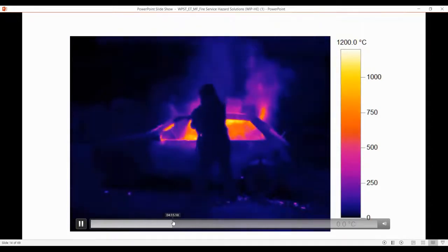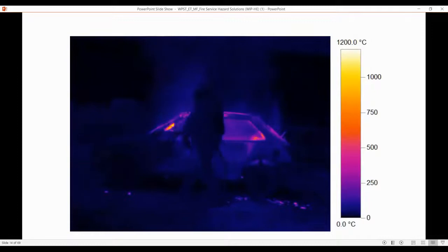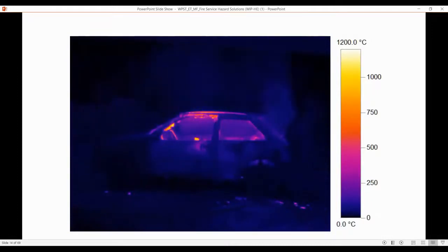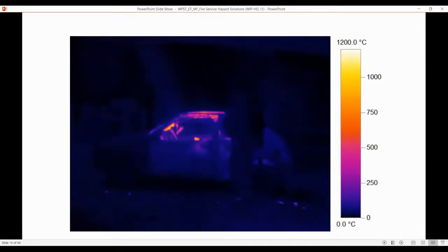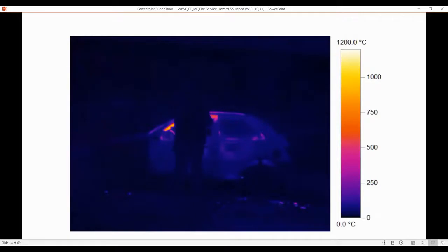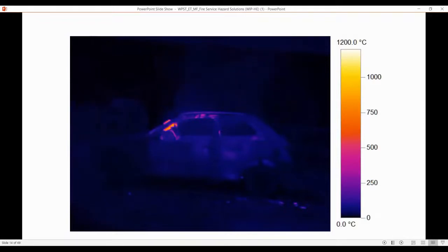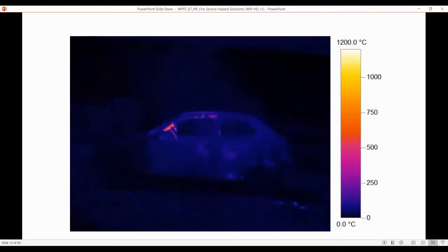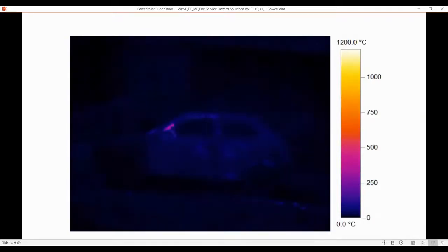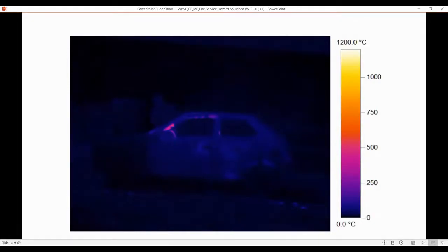Now the firefighter in this video is going to be using a 20-gallon per minute self-educting nozzle. As you see here, as soon as he starts attacking the fire, you have rapid knockdown and rapid cooling. You can see the heat being dissipated out of that metal, how rapidly it's doing it with very little water, very little solution. So this is at a 1% concentration of F500. Again, he's using a 20-gallon per minute flow nozzle. So as you see, almost instant cooling, rapid suppression of the fire, rapid cooling of the metal, much more so than you're going to get with plain water.